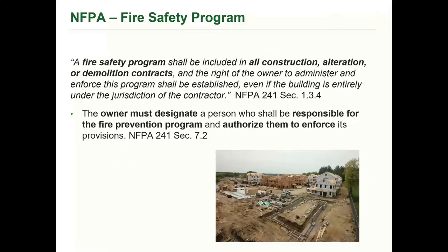NFPA 241 says a fire safety program shall be included in all construction, alteration, or demolition contracts, and the right of the owner to administer and enforce this program shall be established even if the building is entirely under the jurisdiction of the contractor. So this states that every construction project is supposed to have a fire safety program.